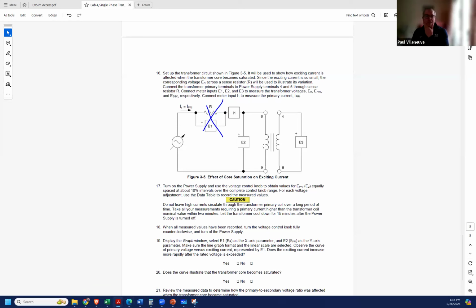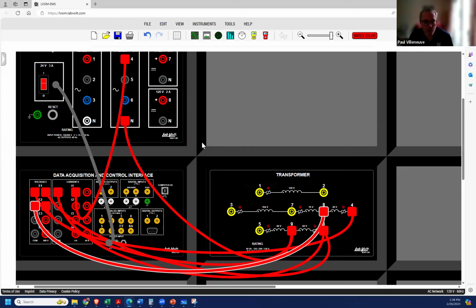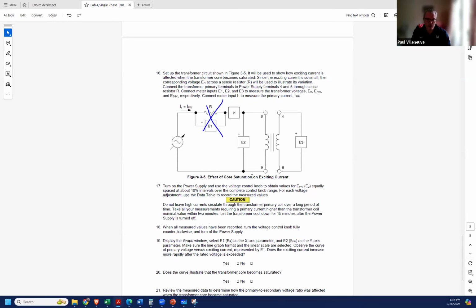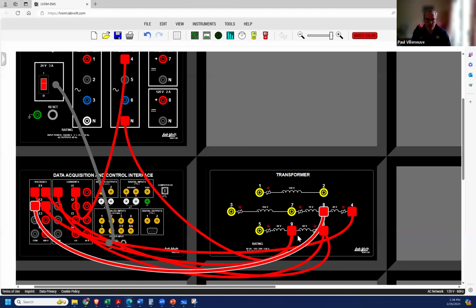Now what I'm trying to do is monitor the circuit to see if it actually saturates. As I push this transformer harder and harder, I should start to see that the amount of excitation current required to drive rated voltage greatly increases. I'm applying the voltage across terminals 6 and 9. If I look over here, 6 and 9 is only rated for 60 volts, but I'm actually pushing it to 120 volts, doubling the nominal rating, because I really want to see the effects of saturation. If I only ran it across both windings, I wouldn't necessarily see it.